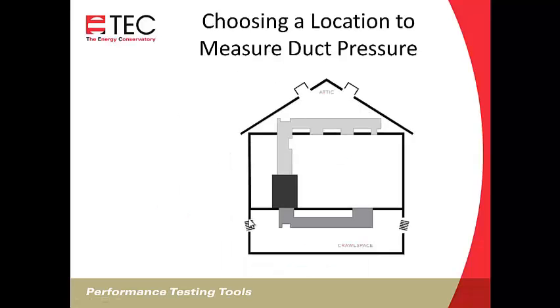So choosing a location to measure duct pressure, typically that's measured with a static pressure probe that came with your duct blaster system. So this is what our static pressure probe looks like. It's got a magnet on it that helps you attach it to ductwork. It's got a 90 degree turn so you can point it into the airflow. It's got a sealed, bullet-shaped end on it. So the air will come across, there's four holes in there for measuring the static pressure.